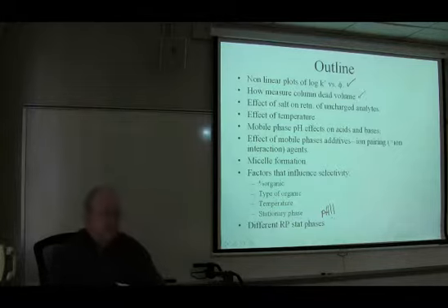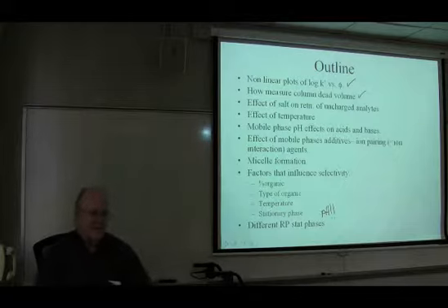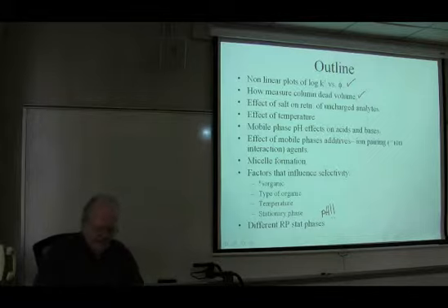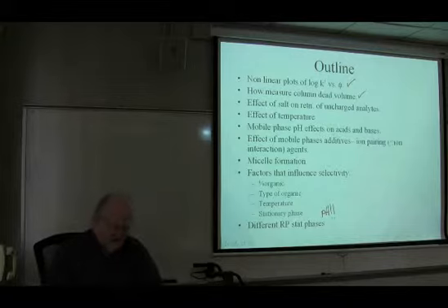Another issue is, how do you measure the dead volume? In gas chromatography, you can almost inject a little methane. Methane at 50 degrees centigrade is not retained on anybody's stationary phase, really. And so you can always measure the dead time of your system by injecting a little methane. But we have a much more difficult time finding something that's unretained in reverse phase chromatography, and I'll show you some of the choices. Then we'll talk about the effect of salt.